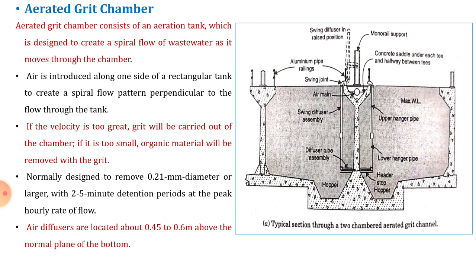An aluminium pipe railing is also provided. Concrete saddle under each tee and halfway between the tees is also provided. If velocity is too great, grit will be carried out of the chamber; if it is too small, organic material will be removed with the grit. The chamber is normally designed to remove 0.21 mm diameter or larger particles with a 2 to 5 minute detention period at peak hourly flow rate. Air diffusers are located about 0.45 to 0.6 meters above the normal plane of the bottom.